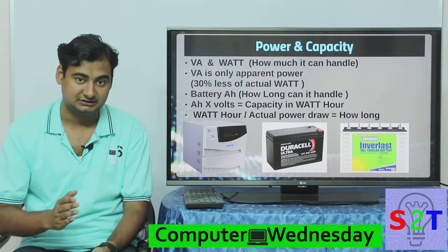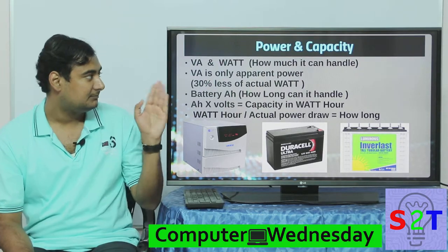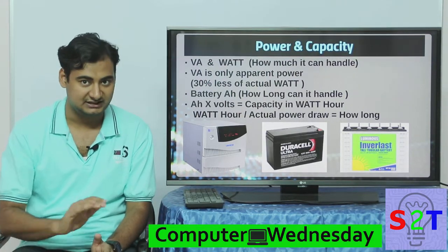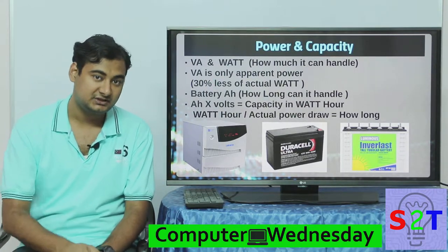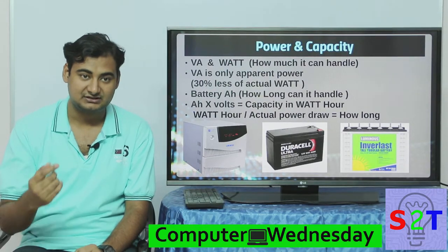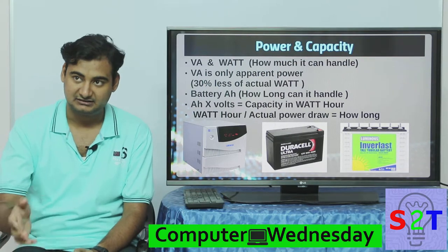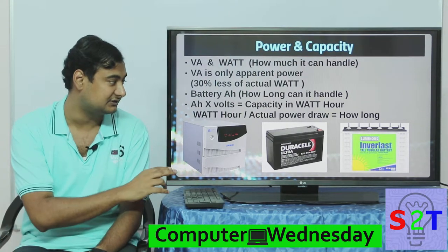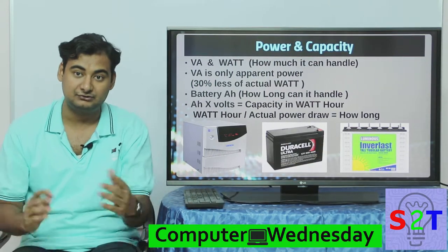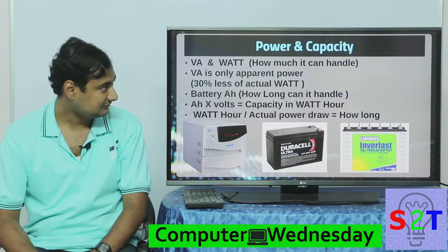Quick summary: power is measured in VA — go 30% below that for your watt capacity. For battery, multiply amp-hours by voltage at the individual battery level, then count how many batteries you have. Some UPS units have dual batteries at the same voltage; some have batteries in series which increases the voltage. So it's a good idea to calculate at the battery level first, then scale up by the number of batteries.